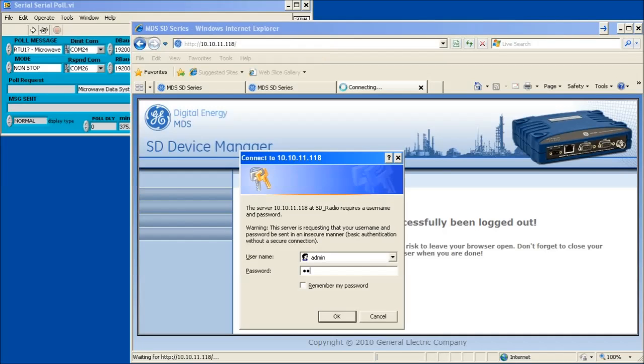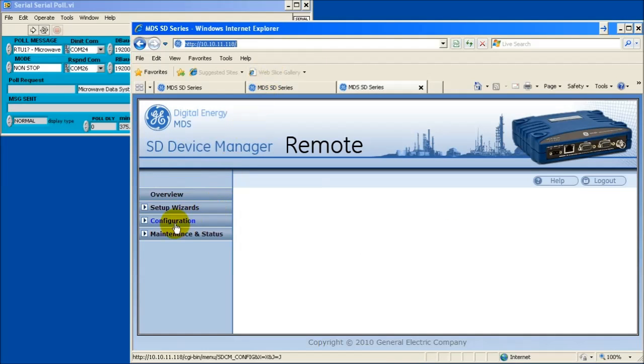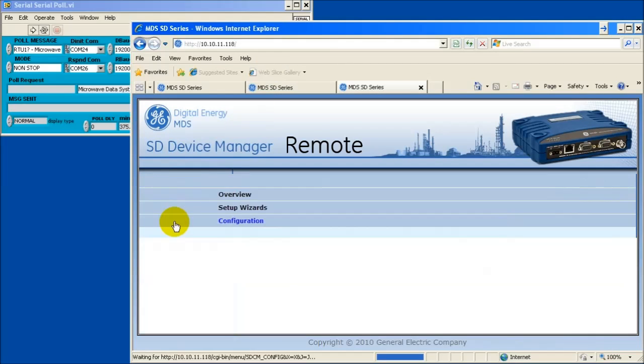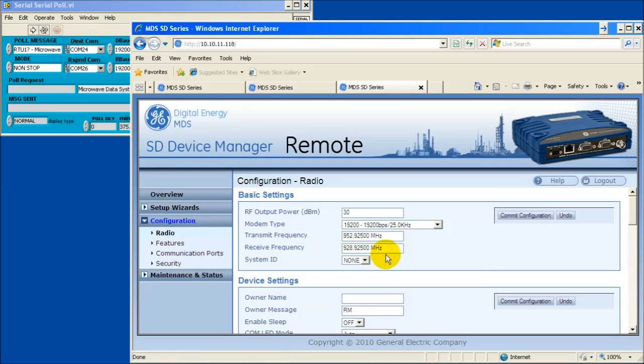Open a web browser to the remote radio. Navigate to the basic settings window by selecting configuration, then radio. Set the remote radio's frequency to match those of the access point radio. For example, TX of the access point radio equals TX of the remote radio, and RX of the access point radio equals RX of the remote radio.